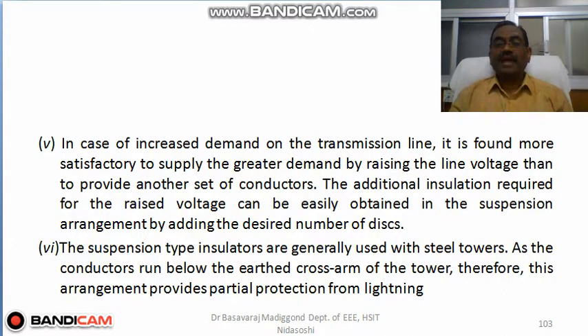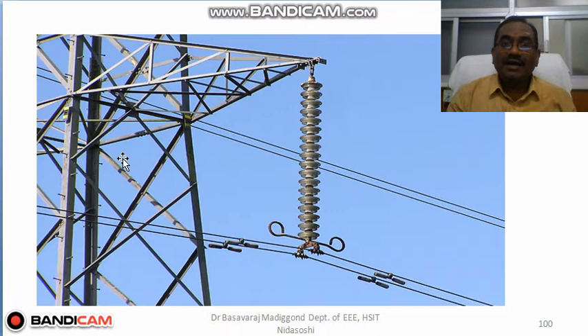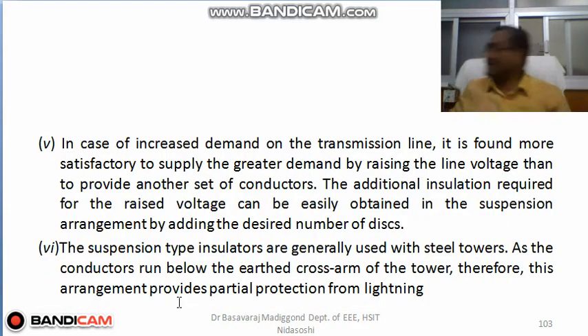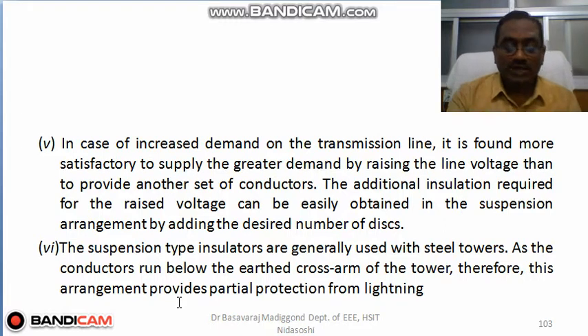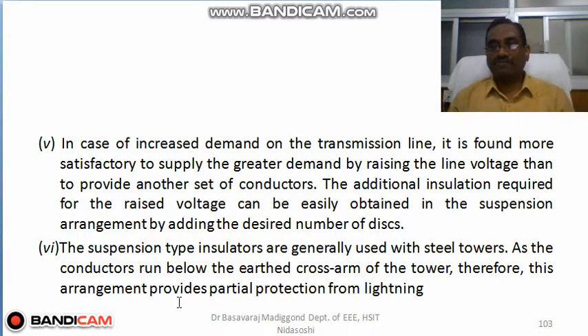Okay, as the conductors run below the earthed cross arm like this. Earthed cross arm in the sense, this is a cross arm. It is connected to the tower, and the tower is erected on the ground. That means it is connected to the ground only, right? So these conductors run below these insulators, correct? The suspension type insulators are generally used with steel towers, as the conductors run below the earthed cross arm of the tower. Therefore, this arrangement provides partial protection from lightning also. Okay.